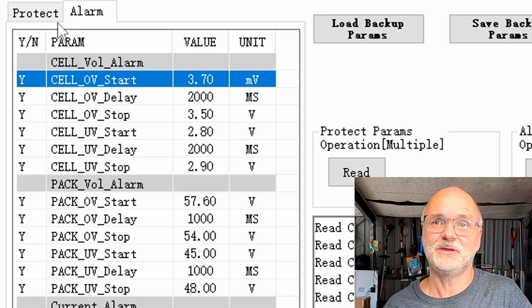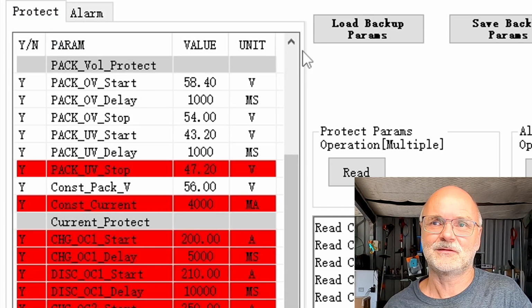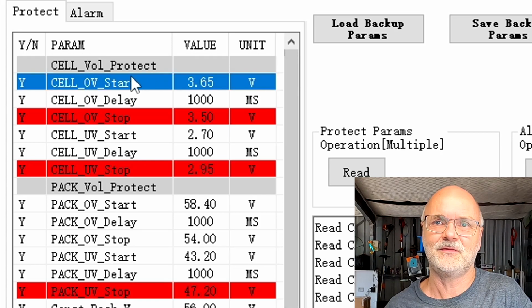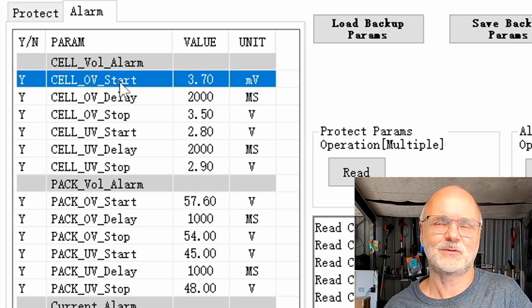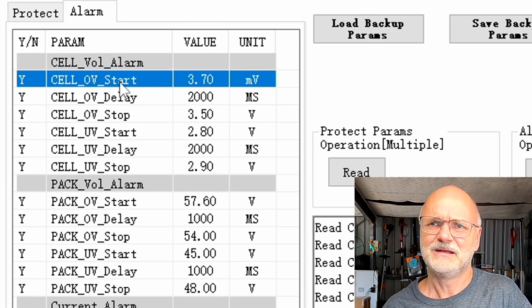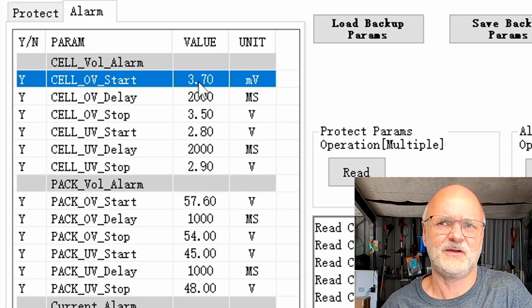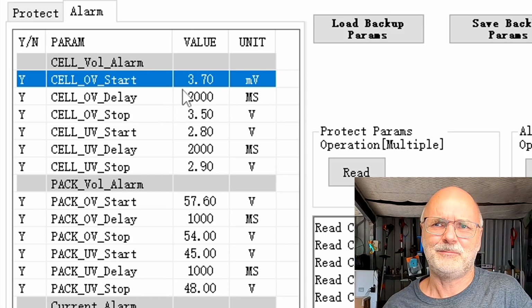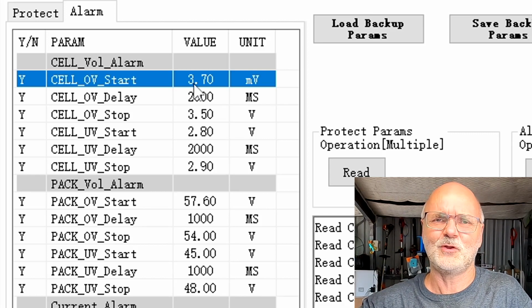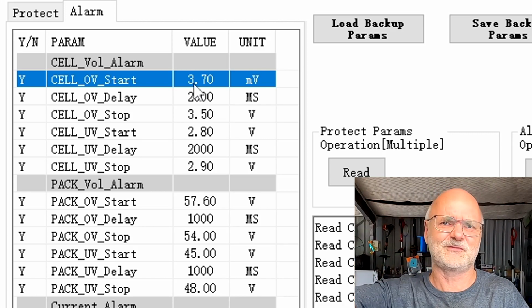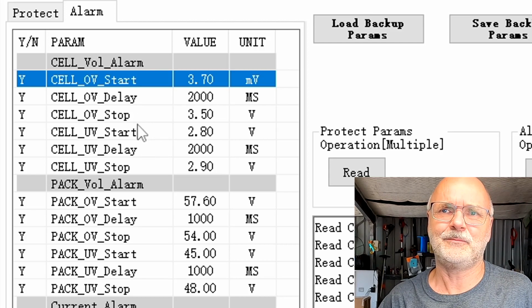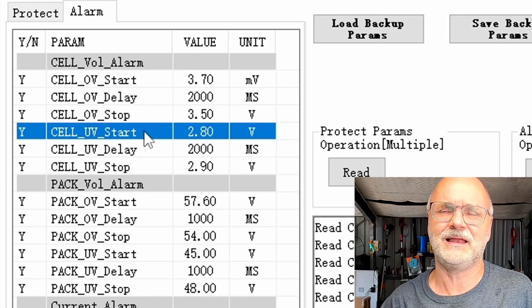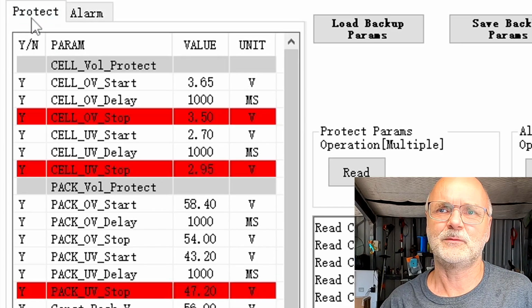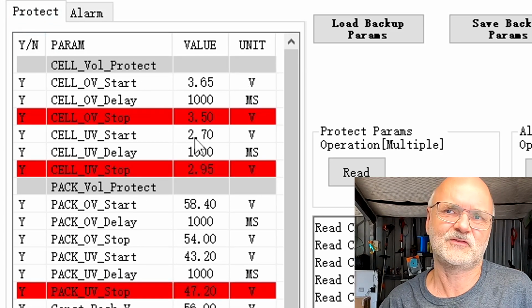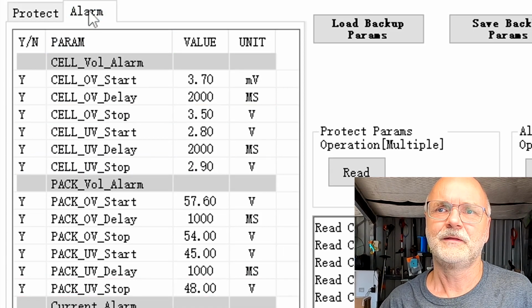But why do we turn off the battery already at 3.65 volts? As we can see here, this is the protection setting, 3.65, but the alarm comes on at 3.70. This makes no sense at all, right? This should come on at 3.6 or 3.55, whatever you want to set it to. But 3.7 is far over the turn-off voltage already, so this parameter is wrong. Again, these are just alarm parameters. The alarm comes on at 2.8, and when we have a look at the protection, it is at 2.7, so this seems to be working.